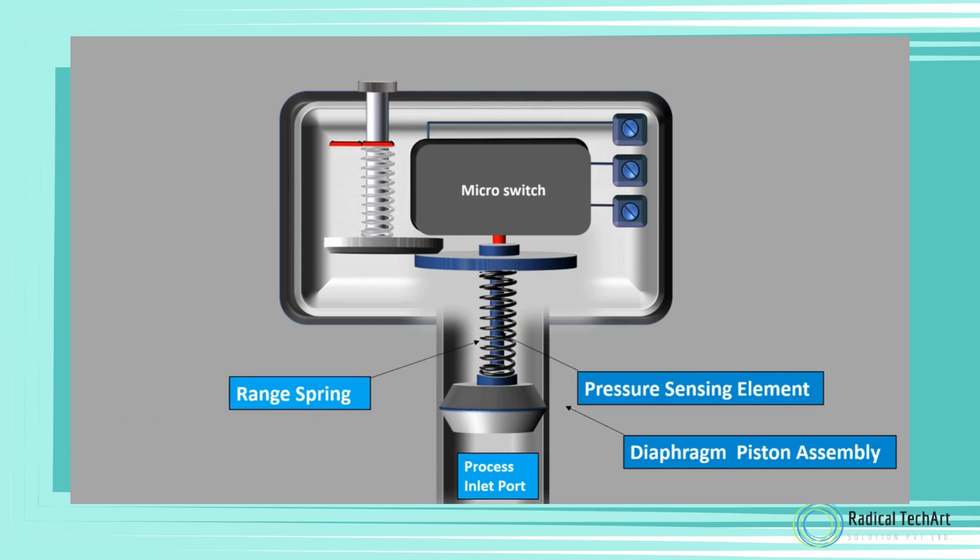Range spring - the range spring counters the force from the fluid. It is preloaded to match the operating pressure of the fluid. The switch only activates when the force from the fluid pressure exceeds the force applied by the spring.